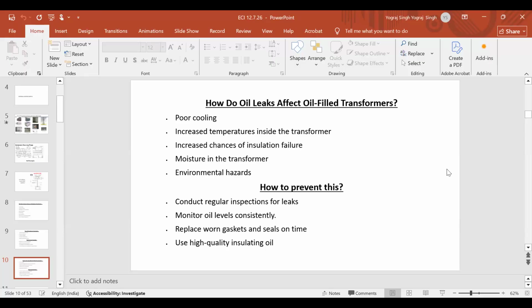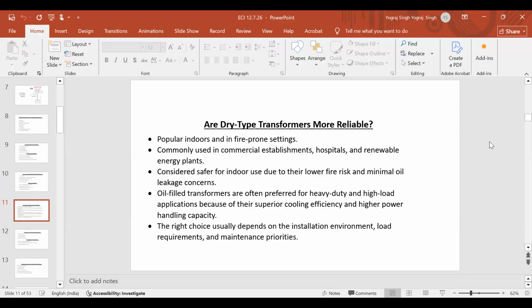Now, if there are so many problems with oil type transformers, then what will happen with my closed spaces, my cinema halls, my hospitals and other places where there is no space outside? Then we'll use dry type transformers. Here the windings are covered in dry insulation. There is some compromise in heat taking capacity, carrying capacity. It is costlier also, but there is no alternative but to keep it underground in the multi-storied buildings, in the basements. That is where you provide dry type transformers.